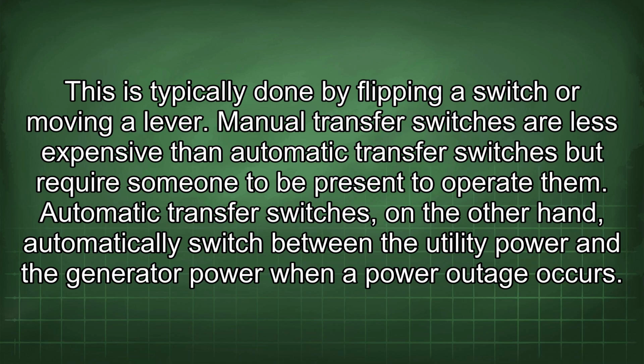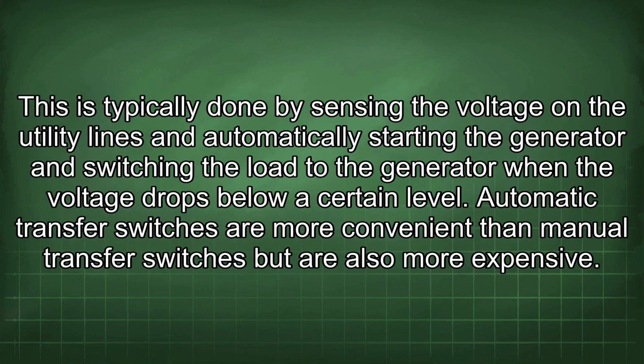Automatic transfer switches, on the other hand, automatically switch between the utility power and the generator power when a power outage occurs. This is typically done by sensing the voltage on the utility lines and automatically starting the generator and switching the load to the generator when the voltage drops below a certain level. Automatic transfer switches are more convenient than manual transfer switches but are also more expensive.